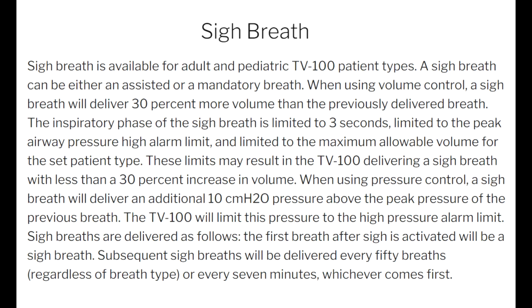When using volume control, a sigh breath will deliver 30% more volume than a previously delivered breath. The inspiratory phase of the sigh breath is limited to 3 seconds, or the peak airway pressure high alarm limit, or the maximum allowed volume for the set patient type. These limits may result in the TV-100 delivering a sigh breath with less than 30% increase in volume. When using pressure control, a sigh breath will deliver an additional 10 centimeters of water pressure above the peak pressure of the previous breath. The TV-100 will limit this pressure to the high pressure alarm limit.